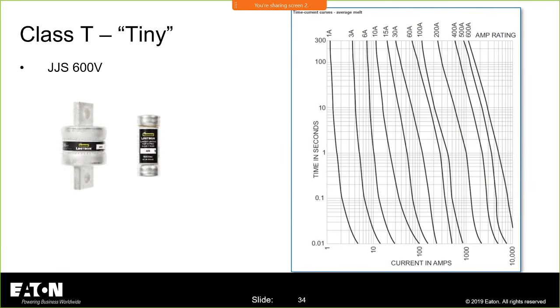But remember, love at first sight. Look at those curves. Gosh darn it. They're faster. Now, you know, they probably wouldn't do so good on motors. And you know, think about a residential application, not bad. You don't have a lot of motor inrush, and heavy industrials might have a little bit of trouble. But again, I love the way these things come down and the curve goes in like that. And if you want to talk about incident energy reduction, in that example that I showed you where we plotted those curves, the class T was nice and tight to the left.